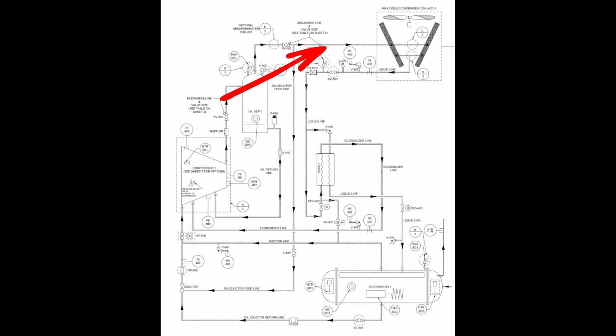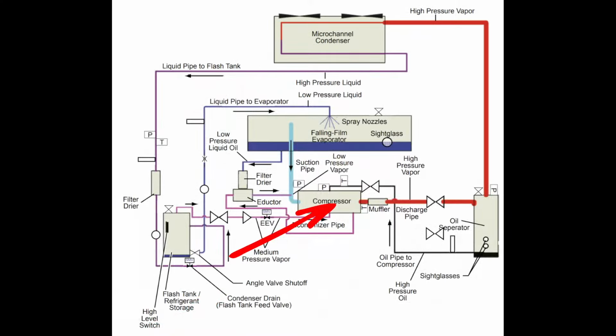We come out and go into our condenser, and you'll see that this has a T right here. So this is our hot gas coming off of the discharge, superheated discharge vapor, back to the eductor to then get our oil return. All right, so oil return circuit, that's the same. They made it look slightly different.